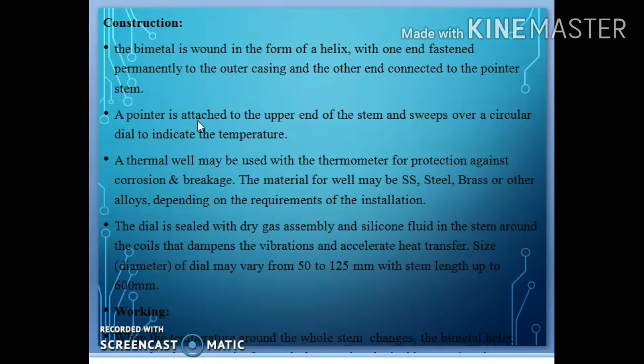The dial is sealed with dry gas assembly, and silicone fluid in the stem around the coils dampens and minimizes the vibrations and accelerates the heat transfer between the stem and bimetallic element. The size of the dial may vary from 50 to 125 mm, with stem length up to 600 mm. When the temperature around the whole stem changes, the bimetal helix expands and rotates at its free end, thus turning the inside stem and pointer to a new position on the dial.